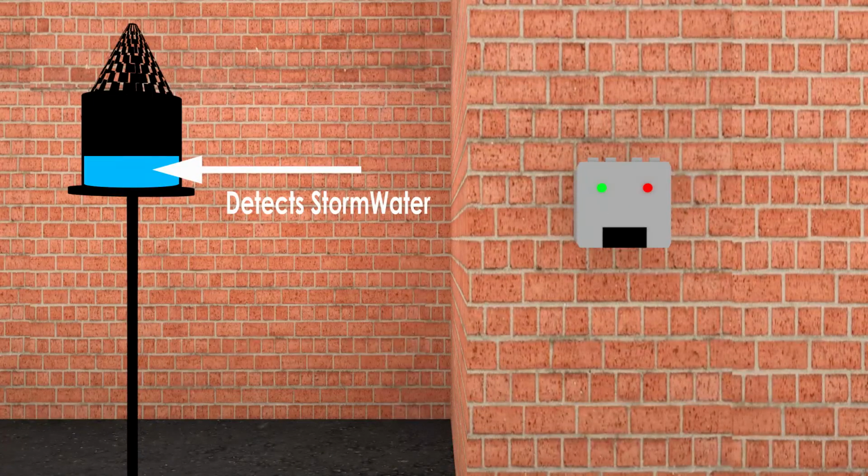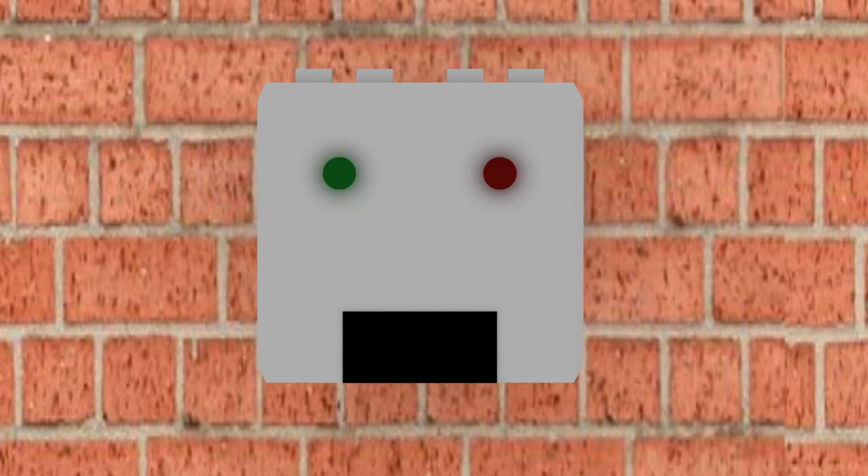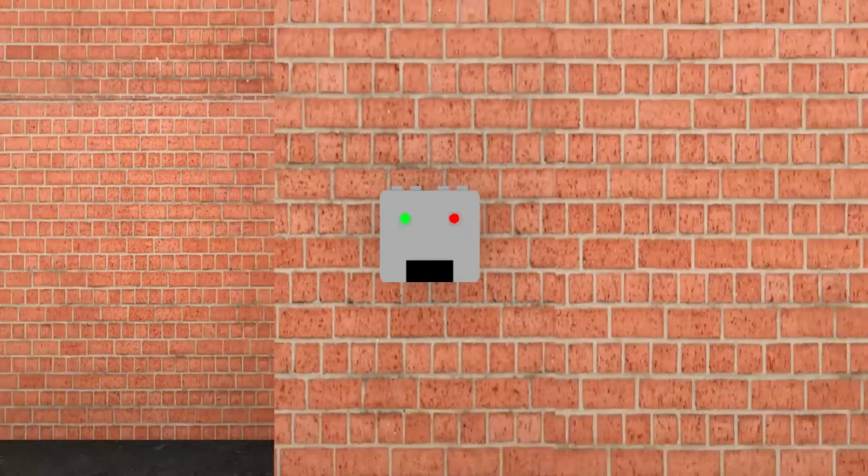The storm switch senses when a storm event has taken place or stormwater has fallen and signals the controller. The storm controller takes the signal from the storm switch and changes to storm mode by controlling the diversion method, keeping track of events, and providing status information. Storm mode is indicated by the changing of light colors on the storm controller unit from green to red. At the same time, the storm controller changes the operating state of the storm diverter.